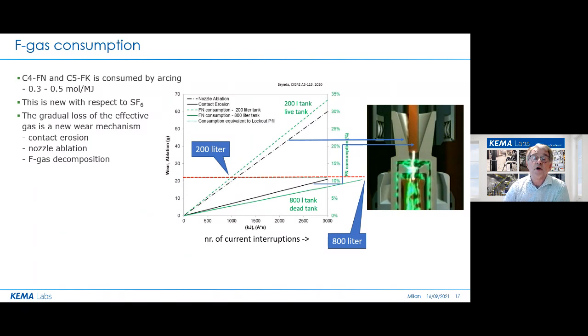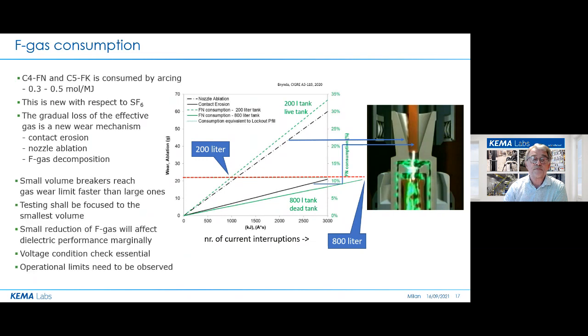In case of a 200-liter tank, which may apply for a live tank breaker, we see that the limit is reached already at this point, just before the end of life of the nozzle has been reached, whereas a much bigger, let's say a dead tank breaker, reaches that point only at that point in time. So we see that a small breaker reaches the gas wear limit faster than large ones.